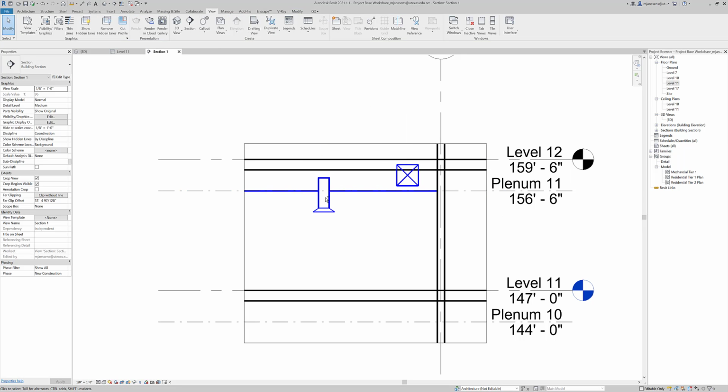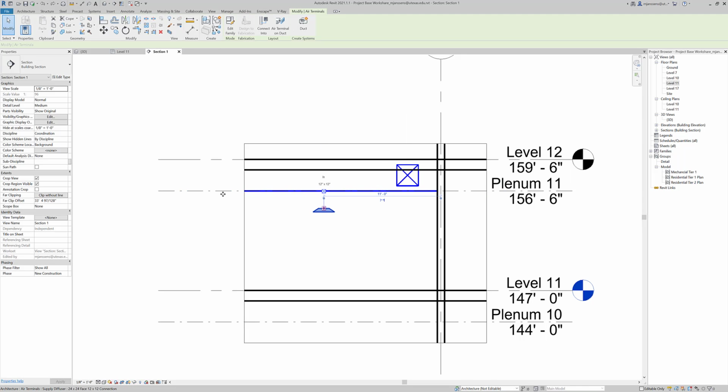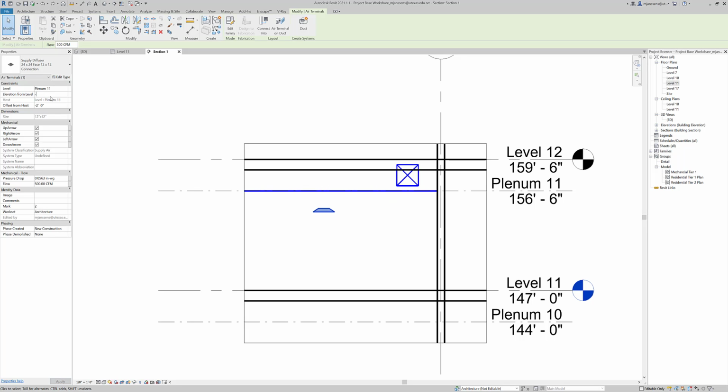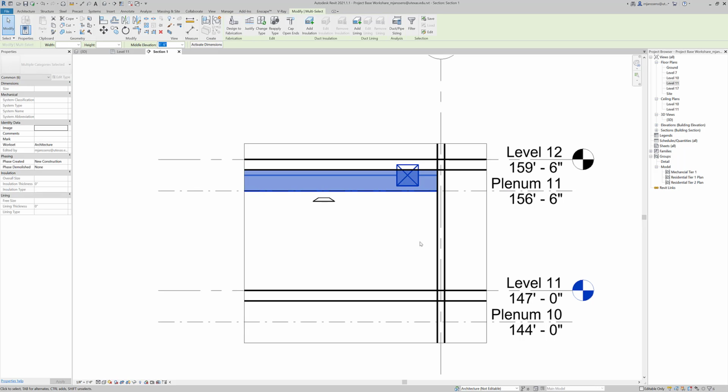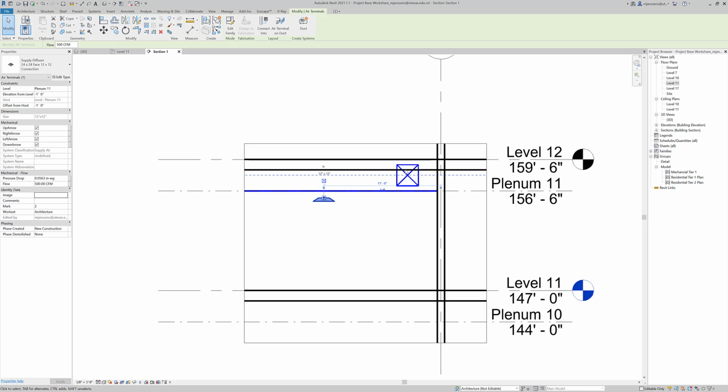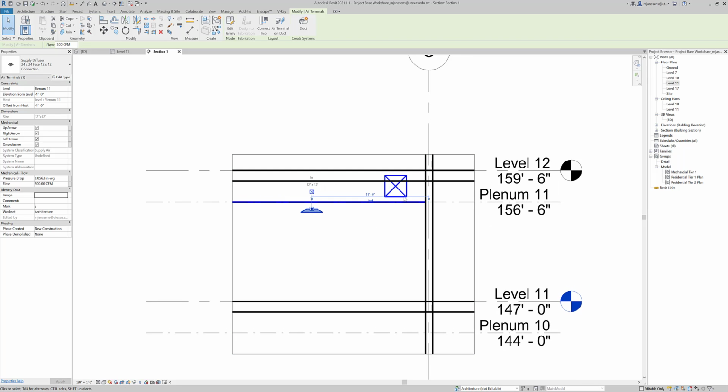So I think a faster route is to change this still to like -1 or -2 feet, and then I actually want to ungroup all this stuff because it seems to have a ton of difficulty connecting air terminals to groups, because these are grouped as duct systems, and it tries to shoot all over the place. So if you're having trouble with it, that's my recommendation. Backpedal a little bit, ungroup your elements, and then we'll repaste them at all the levels we need to.